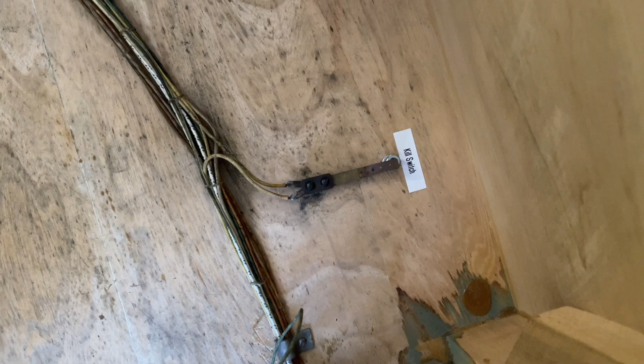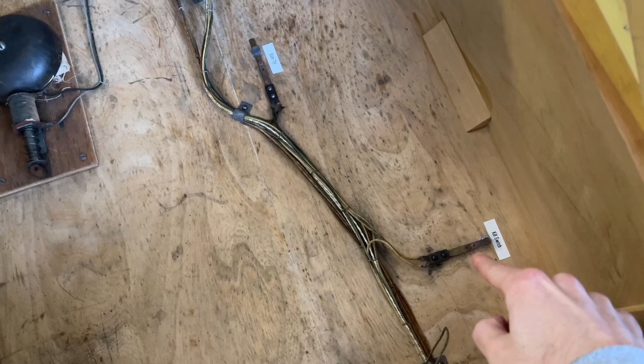So the way to wire this machine so that everything turns off is we need to move this switch from the secondary side of the transformer to the primary side, because we need to break the circuit that this cord is part of. So what we need to do is install the switch before this cord gets to the transformer.